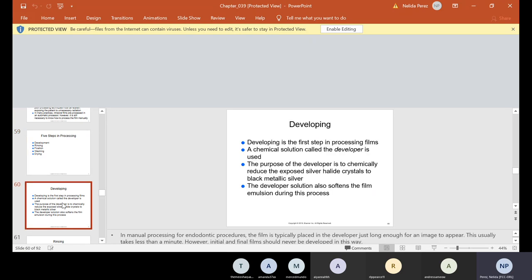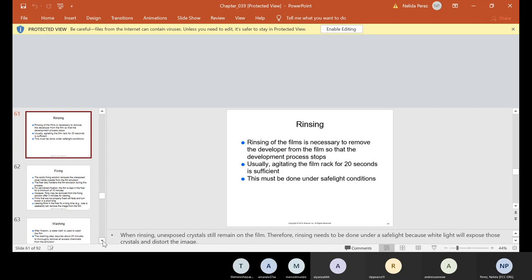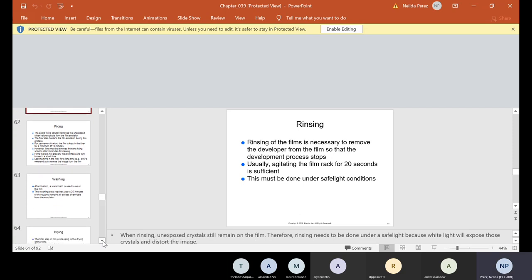Developing is the first step. A chemical solution called the developer is used to chemically reduce the exposed silver halide crystals to black metallic silver. The developer also softens the film emulsion during processing. Then comes rinsing — rinsing the films is necessary to remove the developer so that the development process stops. Agitating the film rack for 20 seconds is usually sufficient, and must be done under safe light conditions. When you put film in the automatic processor, all of that is happening — you can see the tanks labeled developer, fixer, wash one, and wash two.